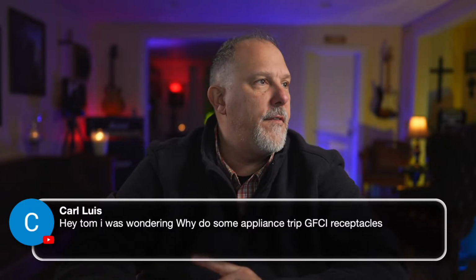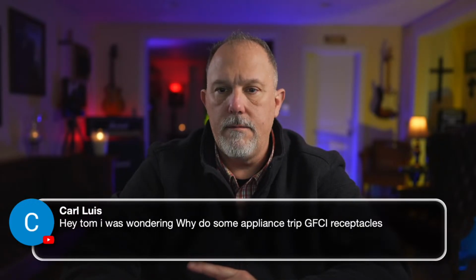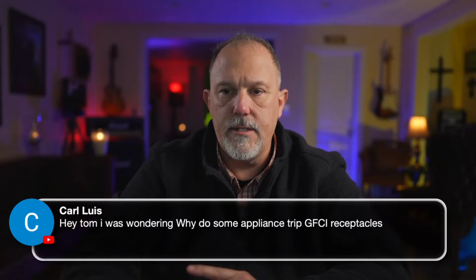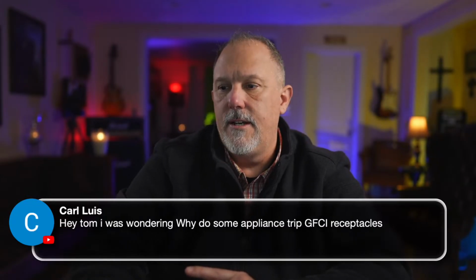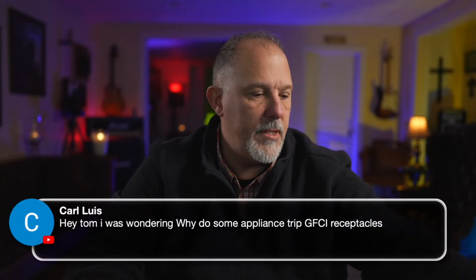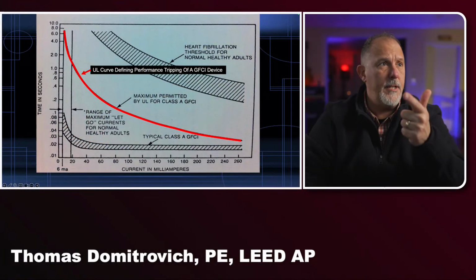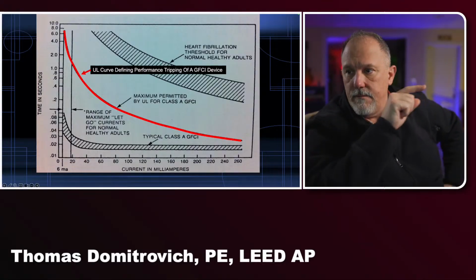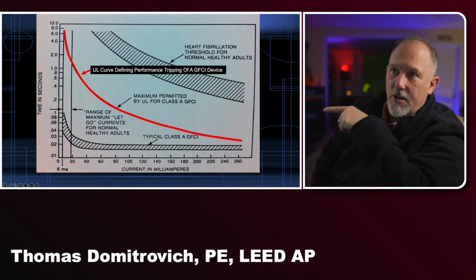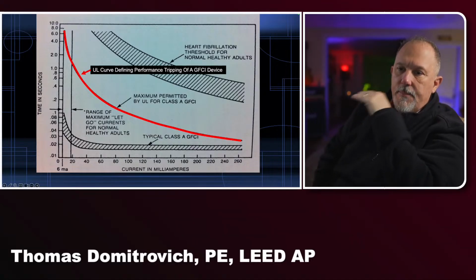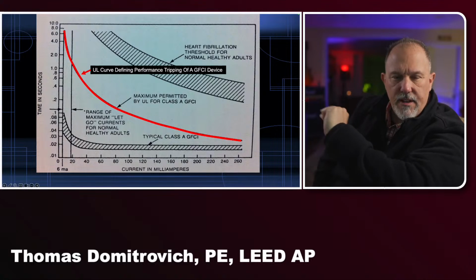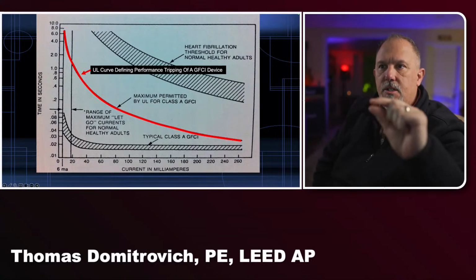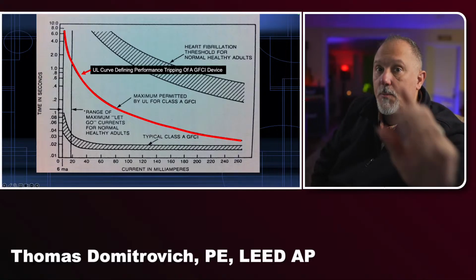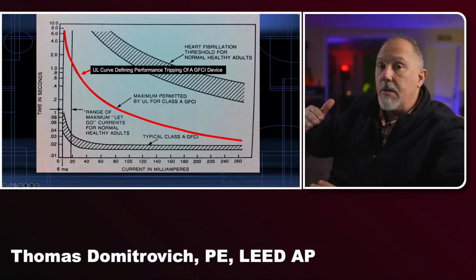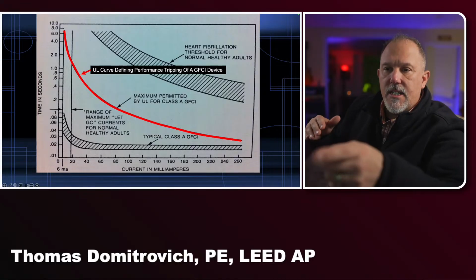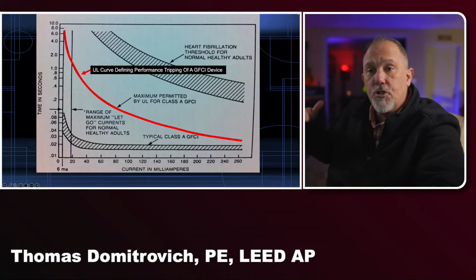And, oh, here we go. Fundamentals of GFCI. No, that's not it. Yes, here it is. Found it. All right, so if you see in this curve, you have the typical Class A GFCI response time, which is really fast. Now, that response time is looking at a 60 hertz, but also if I have higher frequency currents. And there's the maximum permitted by UL. You see that red portion of the curve.